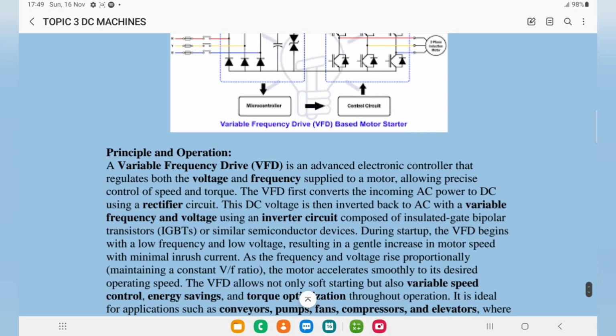The principle of operation is that it's an advanced electronic controller that regulates both the voltage and frequency applied to the motor, and with this it allows precise control over speed and torque. First, the incoming AC power is converted to DC by a rectifier circuit. A rectifier circuit can comprise diodes, because diodes in a circuit are responsible for rectifying the voltage. Remember, we convert to DC because DC is stable. This DC voltage is then inverted back to AC with a variable frequency and voltage using an inverter circuit, composed of insulated gate bipolar transistors or similar semiconductor devices.